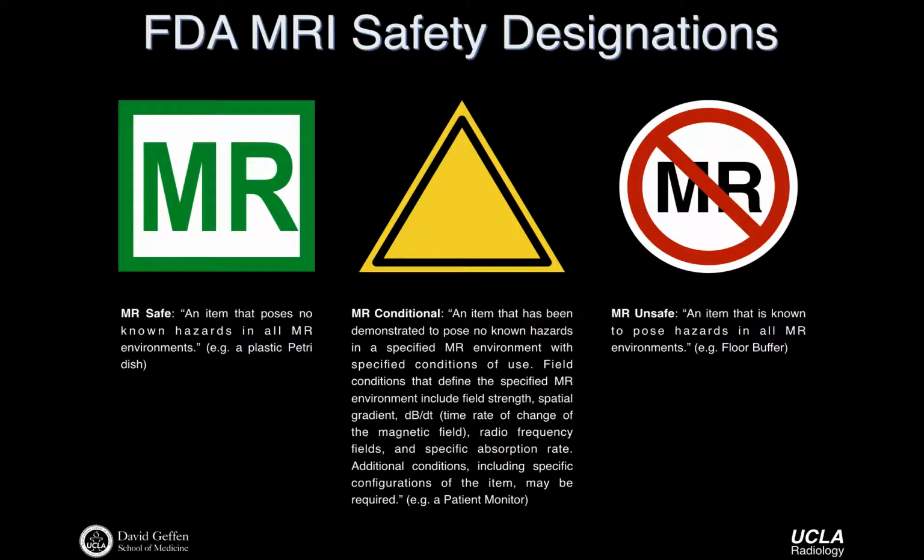It might be acceptable for all use at 1.5T, but not approved for use at 3T. It just depends on what labeling and conditions the company received from the FDA at that time. This is important to me because we do work in MR safety, specifically related to pacemakers and ICDs. These manufacturers are working furiously to produce designs that are increasingly safe and have fewer and fewer conditions associated with them, so I don't think it's very far off that pacemakers and relatively complicated devices may even just be labeled as MR safe.